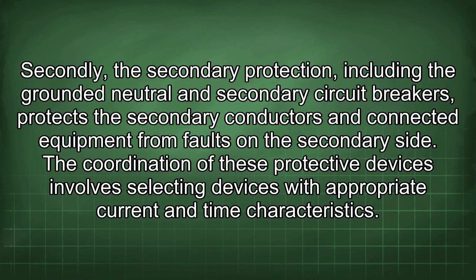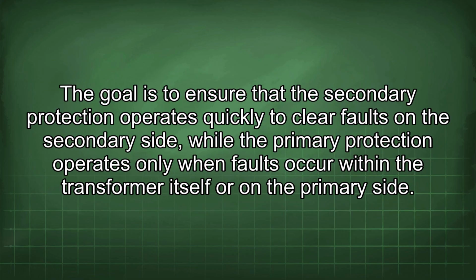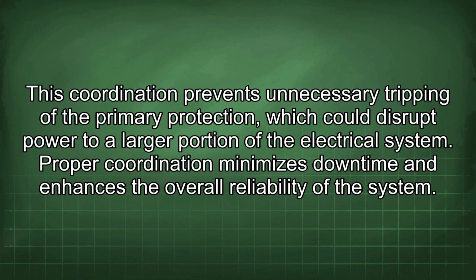The coordination of these protective devices involves selecting devices with appropriate current and time characteristics. The goal is to ensure that the secondary protection operates quickly to clear faults on the secondary side, while the primary protection operates only when faults occur within the transformer itself or on the primary side. This coordination prevents unnecessary tripping of the primary protection, which could disrupt power to a larger portion of the electrical system.